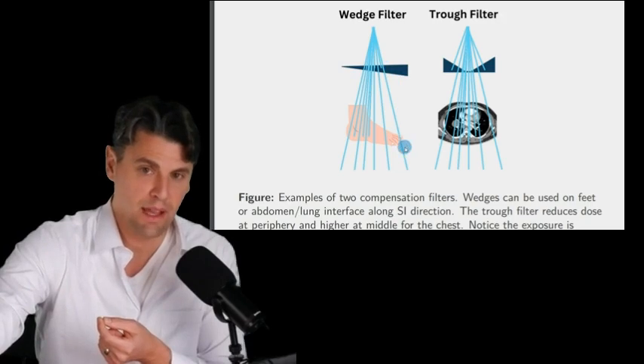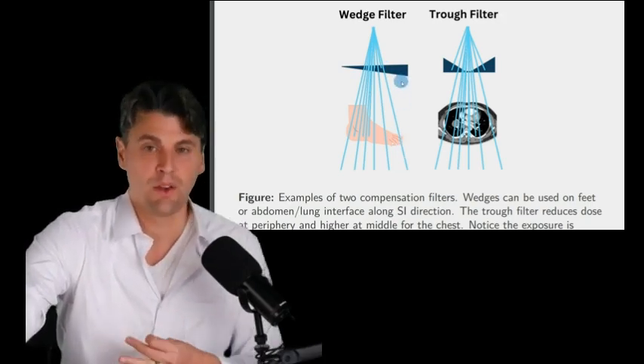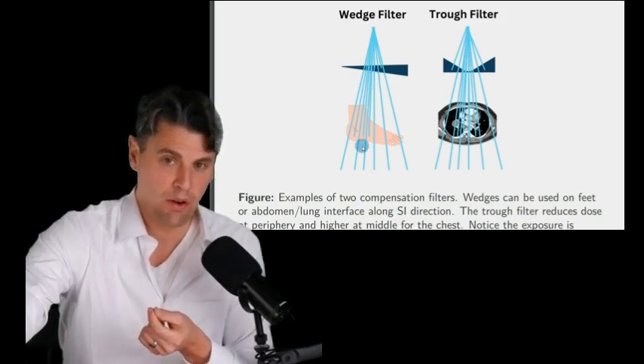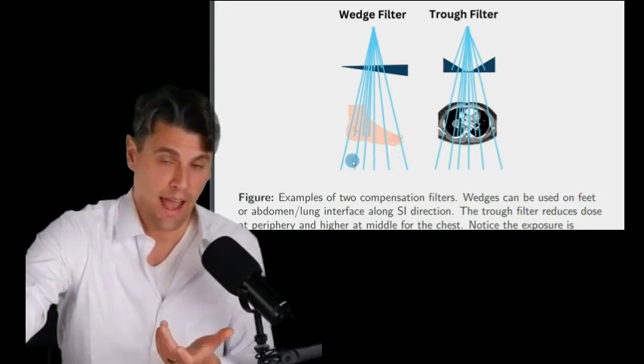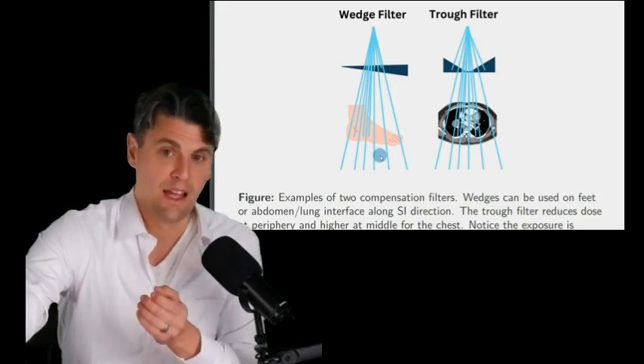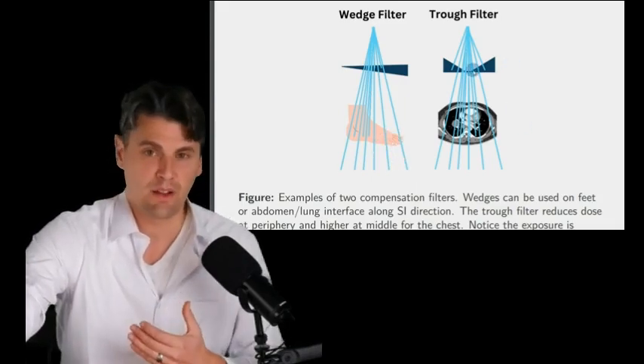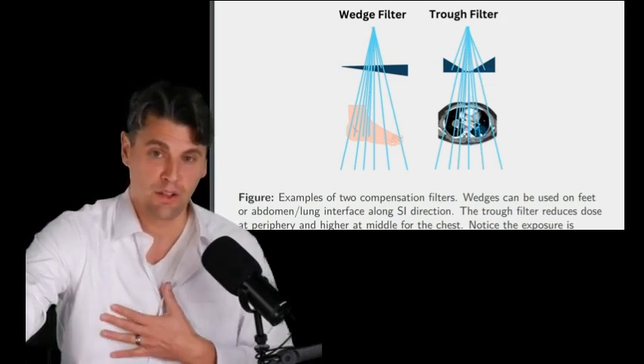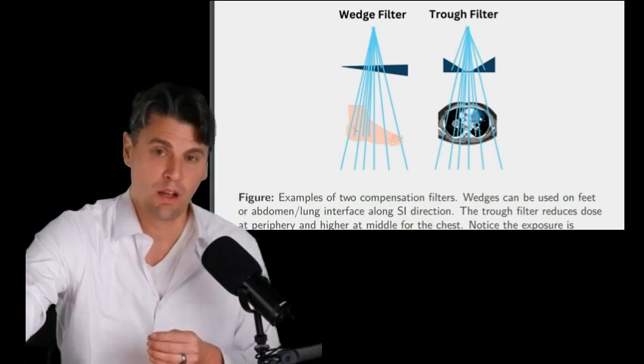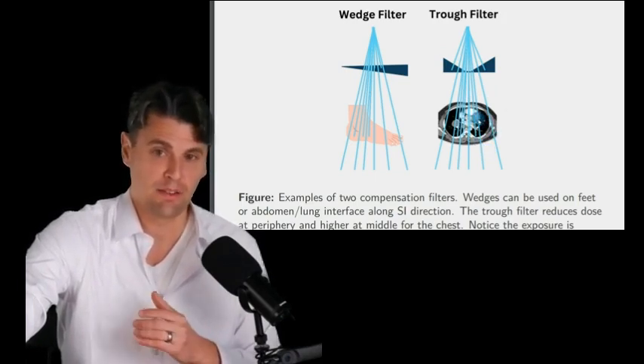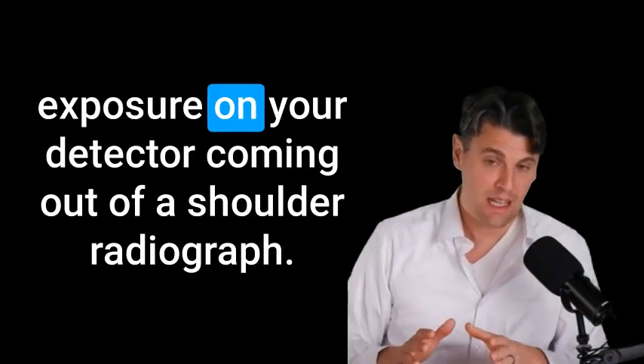If you're imaging a foot, you could use a wedge filter and have a thinner part of that wedge over the thicker part of the anatomy. The idea being that you'd like to have uniform exposure after passing through both this compensating filter and through your patient anatomy. You can use something that's called a trough filter if you're going over the chest because you actually have more attenuation around the heart and less attenuation around the lungs. There's a cool one called a boomerang filter that you can use over the shoulder such that you can have relatively similar amount of exposure on your detector coming out of a shoulder radiograph. That's your whirlwind tour of all the components of an x-ray system.